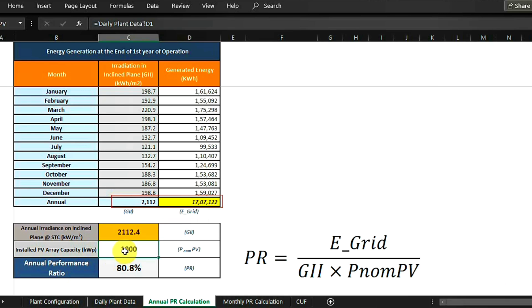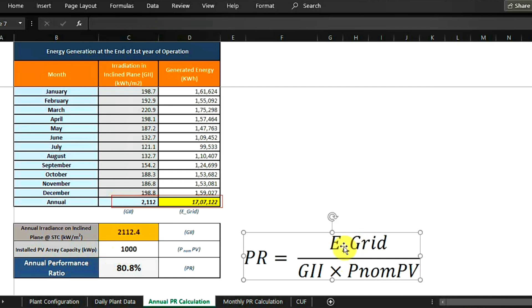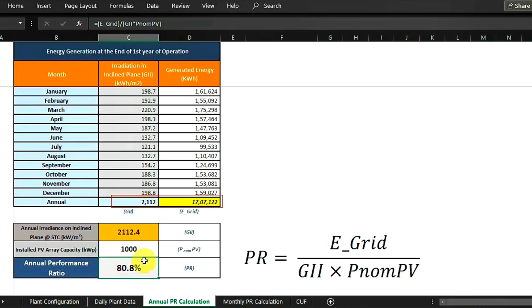As per the formula, the annual radiation value is 2112.4 kWh per meter square and the installed DC capacity is 1000 kilowatt (1 megawatt). So generation divided by global radiation (2112) multiplied by DC capacity (1000) gives 80% — multiplied by 100. When you click on the cell you can see the formula applied. The annual PR comes out to 80%.